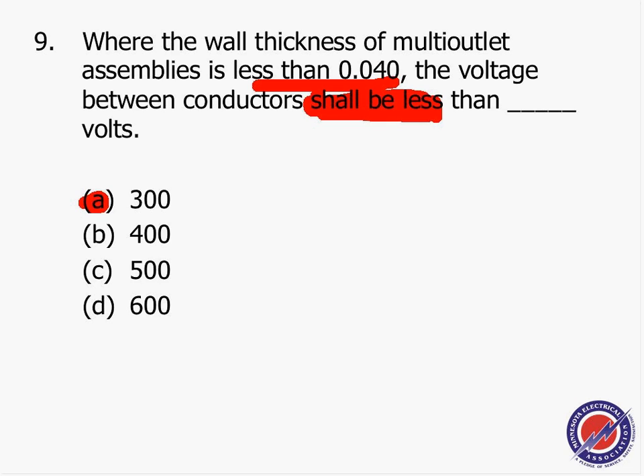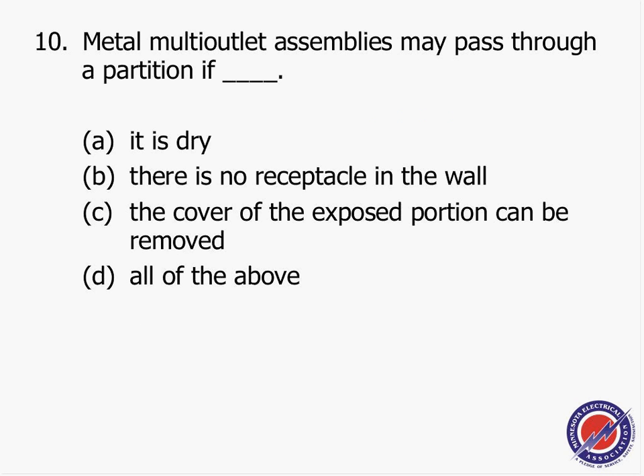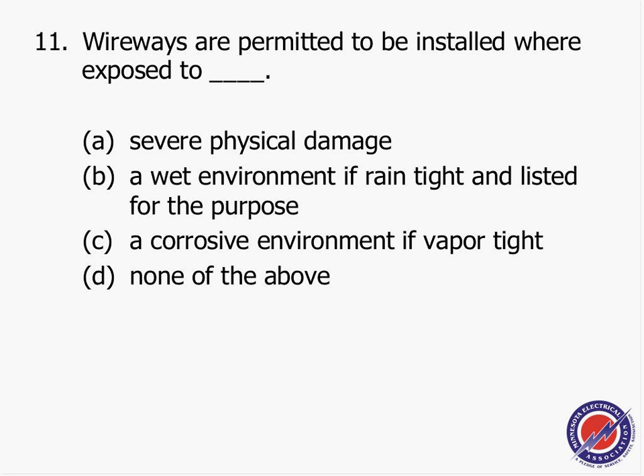Number 9. Any comments with this? Any questions? So limited to 300 volts or less. And a metal multi-outlet assembly may pass through a partition if, D, all of the above: in dry locations, there is no receptacle in the wall, and the cover of the exposed portion can be removed. So pass through, not concealed. Pass through.